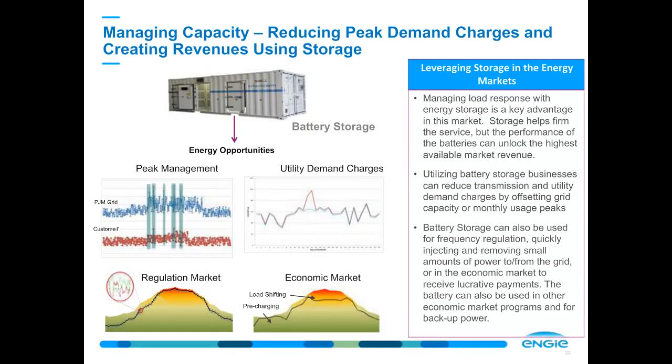The next thing then is managing capacity through creative solutions. And one of them that we're seeing more and more, and in fact we've made an investment in a company called Green Charge Networks, which is a battery storage technology company and algorithm company. Using on-site storage, you're able to, again, if you get this PLC notification, bring down your load during that 2-hour window by whatever your total storage capacity is in the battery that you have on site. So you can manage your peak demand with battery storage.